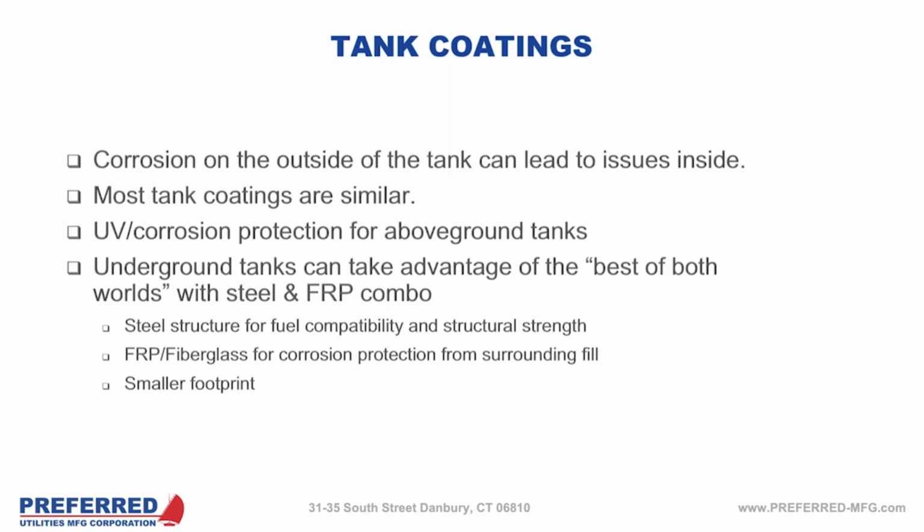And most importantly, when we talk about footprint, I think a lot of people get the idea that it's the actual space it occupies, right? When I'm talking about footprint, one of the most important things is not the total space that an underground tank occupies, it's also the depth. If you have an area where it's not just out on a lawn, where it's maybe in a parking lot or anywhere where a truck can run over it, and you're looking at, say, H ratings or things like that, what we're really talking about here is how close to the surface that tank can be. Because for every foot you push that tank below the surface, whether it's for a concrete cover of some kind, or just depth below the surface so you need a certain amount of fill, that's going to impact the performance of your fuel system. That's another foot that you have to lift the fuel out of the tank by the transfer pumps. So that can actually have a surprisingly large impact on the performance of the system.